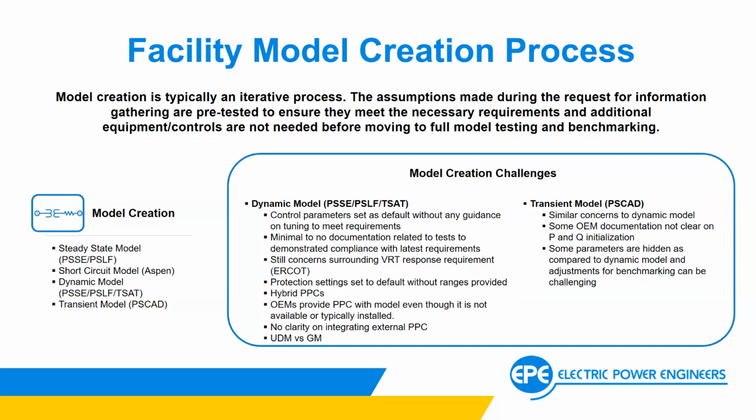Another big concern that has been going around still, in my opinion, is the voltage ride through response requirement, especially in the ERCOT region, with regards to how fast we respond to reactive power during the events, the active power response post event, and things of that nature. I still see a little bit of concern and confusion, maybe from the OEM standpoint, in terms of what the expectations are, and it's a matter of working through that and getting an understanding of how we can best address that moving forward.